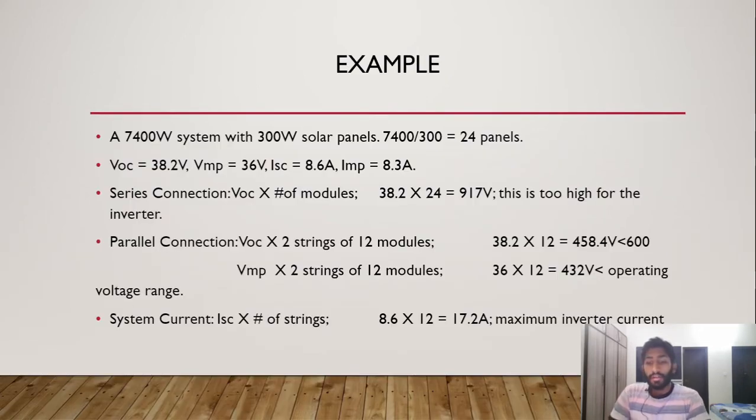Let's look at an example of how you would size an inverter. Let's say we have a 7.4 kilowatt solar system with 300 watt solar panels. How many modules do we need? We divide 7400 watts by 300 watts to give us 24 panels. If we have a series connection, multiplying the Voc of 38.2 volts times 24 modules gives us 917 volts.